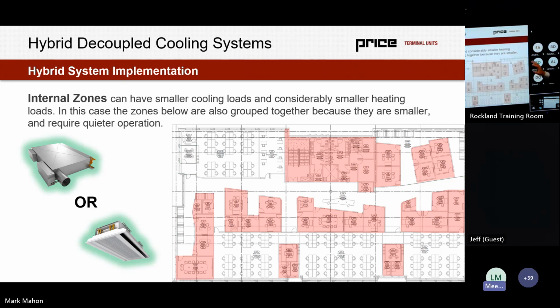And then finally, these internal zones. Internal zones having smaller cooling loads, definitely much smaller heating loads, and also being grouped together because they're smaller, they need quieter operation. We have phone rooms with even 2 occupants or 1 occupant. We have meeting rooms. What would we suggest for these internal zones?